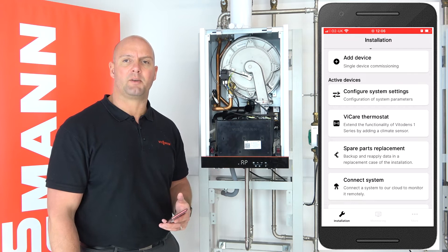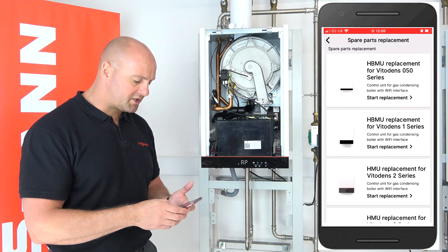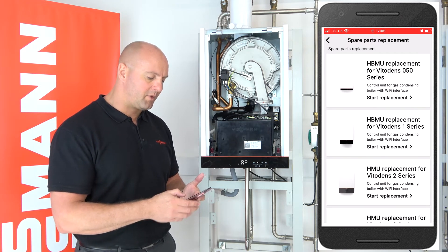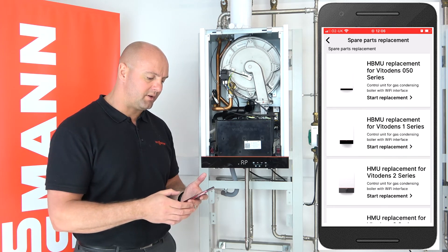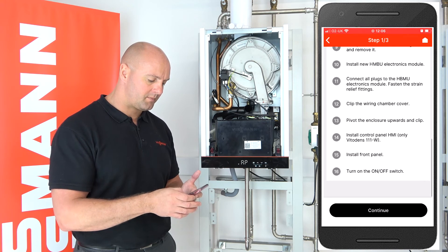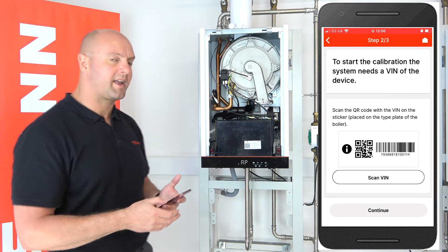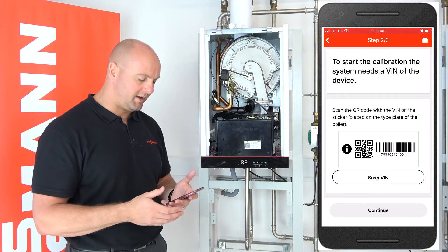Over to the app now to do our commissioning. As you can see on the app, we've got a spare parts replacement section — we click on that. Because we're doing the 100 boiler today, we click on HBMU replacement for Vitodens 1 Series. Click start replacement. It does give instructions there again on how to replace the PCB itself, so we click continue because we've done that part already.